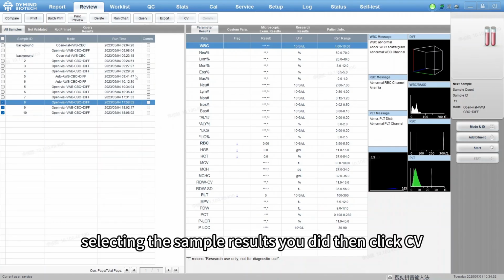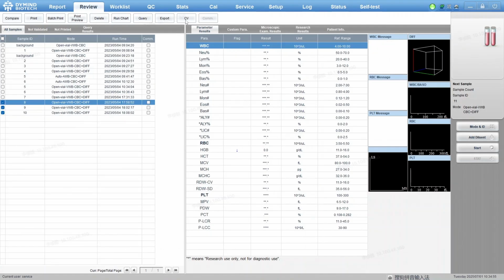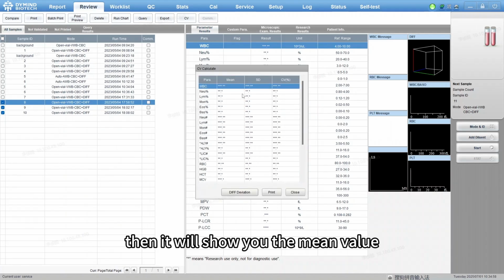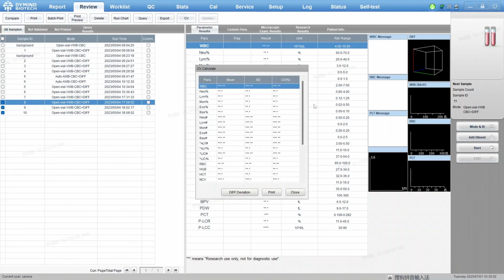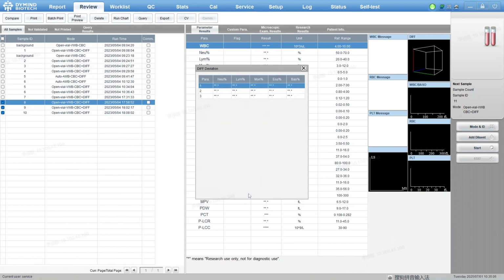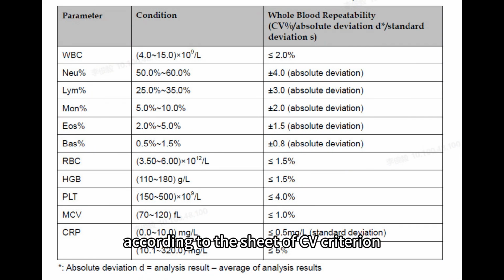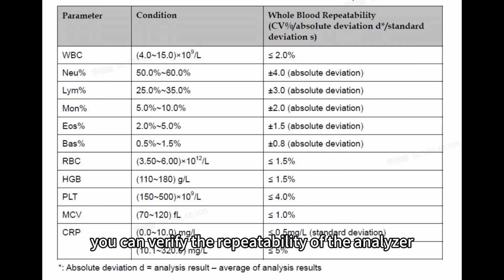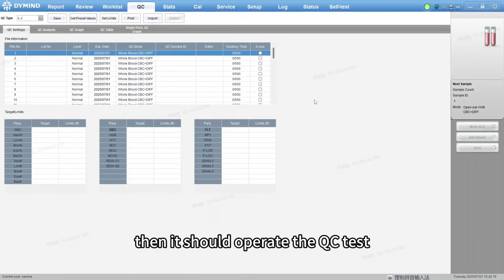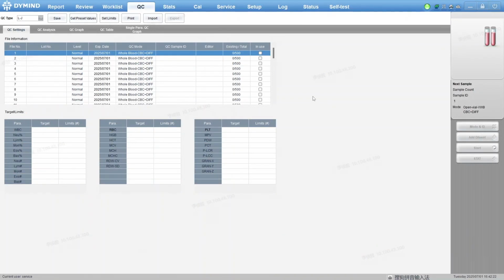Select the sample results you did, then click CV. Then it will show you the mean value, standard deviation, and CV percentage, also the deviation of diff. According to the sheet of CV criterion, you can verify the repeatability of the analyzer. Then operate the QC test.